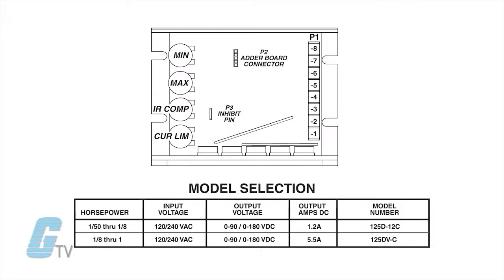These drives can be set up to work with shunt wound and permanent magnet motors up to 90 volts DC with a 120 volt AC input and up to 180 volts DC with a 240 volt AC input.